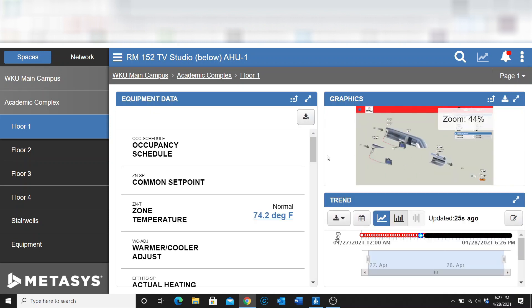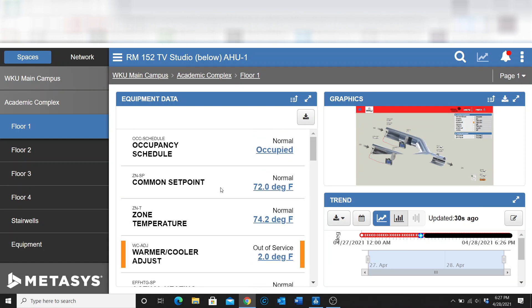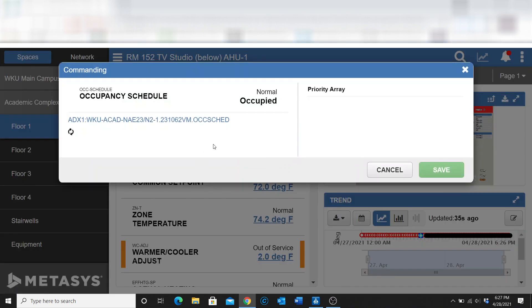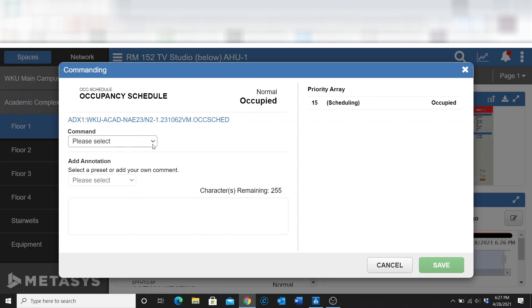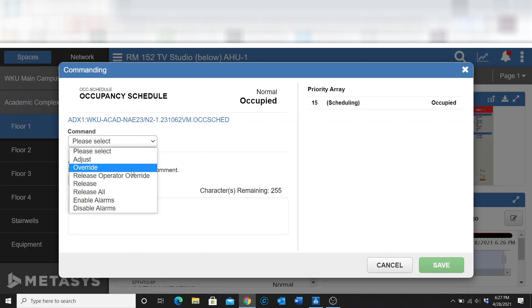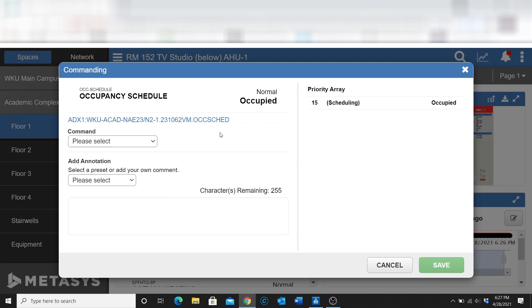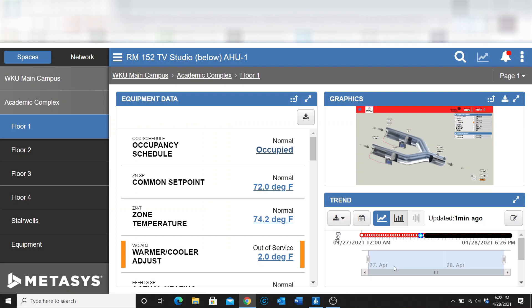We're getting the graphic to come in and we're getting a lot of information about what's going on with that VAV. I can minimize the graphic and go into the text view, where I have all my setpoints and occupancy command. If I wanted to change something, I could just click on it and it gives me the ability to change the command — whether I want to do an adjust and override or whatever I want to do.